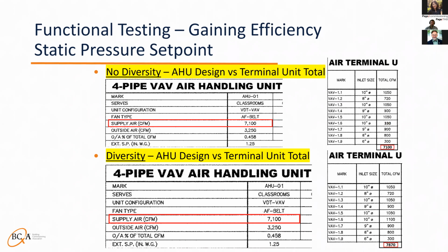That is something different. You really should never command the terminal unit damper unless you are troubleshooting or verifying the damper span. You should never see the sequence saying the BAS should modulate the terminal unit dampers to 100% open. That should never happen. You should always, always, always allow the terminal unit to control to flow set point. This should also be the case for outside airflow, but that is another topic in itself. Anyways, at this point, the AHU should be at its static pressure set point and all the terminal units at their max cooling set point.